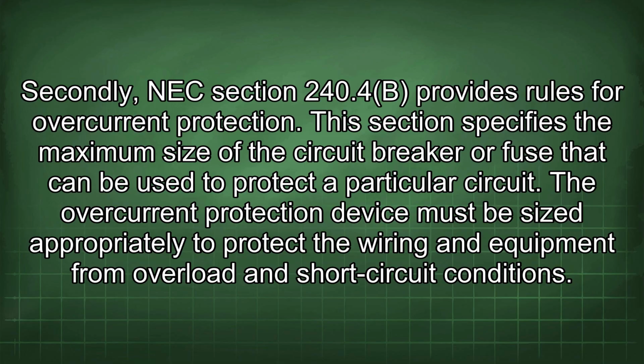Secondly, NEC Section 240.4b provides rules for overcurrent protection. This section specifies the maximum size of the circuit breaker or fuse that can be used to protect a particular circuit. The overcurrent protection device must be sized appropriately to protect the wiring and equipment from overload and short-circuit conditions.